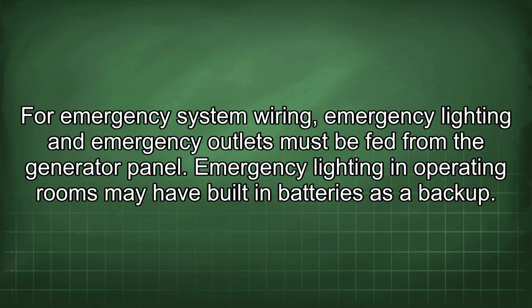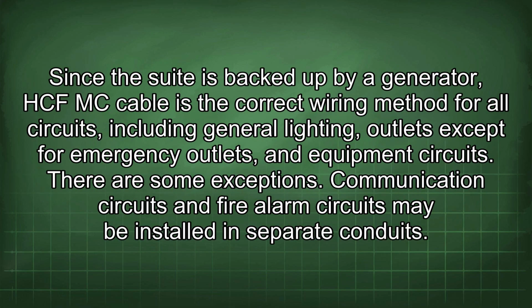For emergency system wiring, emergency lighting and emergency outlets must be fed from the generator panel. Emergency lighting in operating rooms may have built-in batteries as a backup. Since the suite is backed up by a generator, HCF-MC cable is the correct wiring method for all circuits, including general lighting outlets except for emergency outlets and equipment circuits.